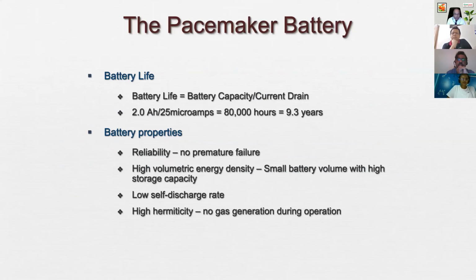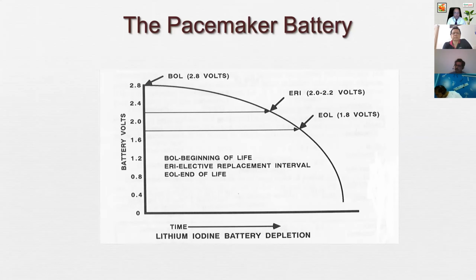They are quite reliable. It's very rare to have a premature battery failure. They have a very good volumetric energy density. They don't usually do much self-discharge, and they have very high hermeticity, which means that there is no gas generation during the operation. So the pacemakers are absolutely safe, but rarely there have been situations where there has been some leakage from the battery and consequently from the pacemaker as well. Usually this battery voltage is maintained for a very long time around the same value of 2.8, and towards the end, pacemakers undergo battery depletion.